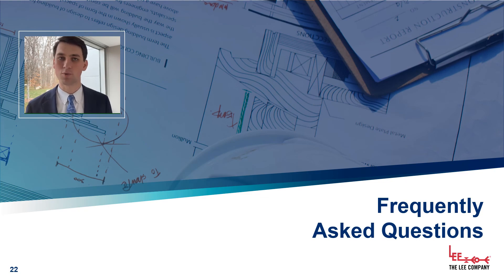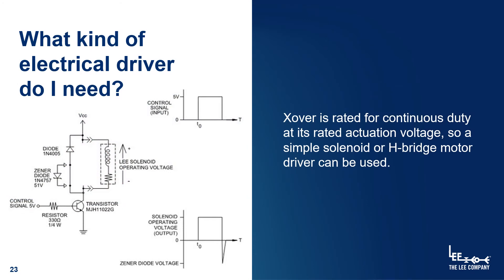Next we'll cover some frequently asked questions about Crossover. By far the most common question we receive is what electrical driver to use. Thankfully Crossover is agnostic to the type of actuation technology you use for its solenoid coil. The valve is rated for continuous duty, meaning you can actuate it and hold it open for an indefinite period of time at the actuation voltage and current. The coil will get warm but this won't damage the valve as long as it's being operated within the ambient temperature range. You could use a basic transistor circuit, a relay, or an H-bridge motor driver chip to actuate the coil.